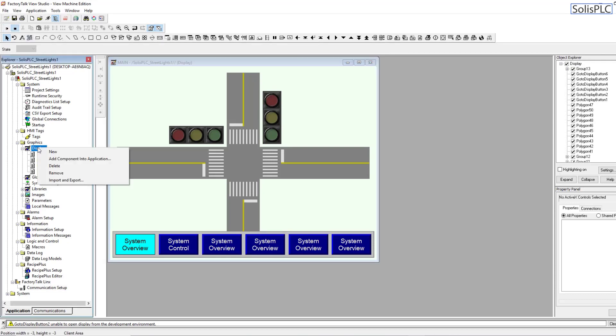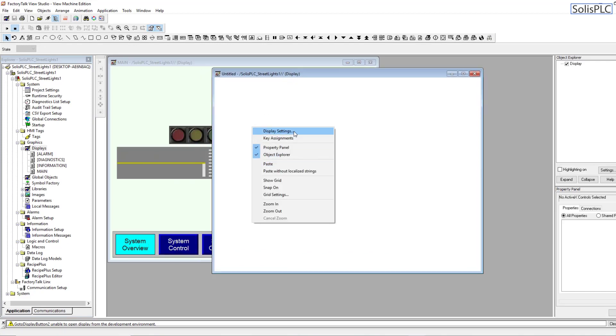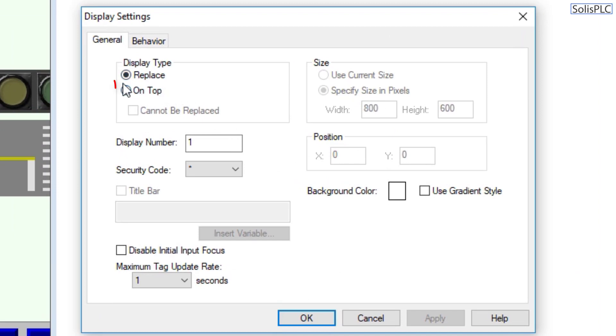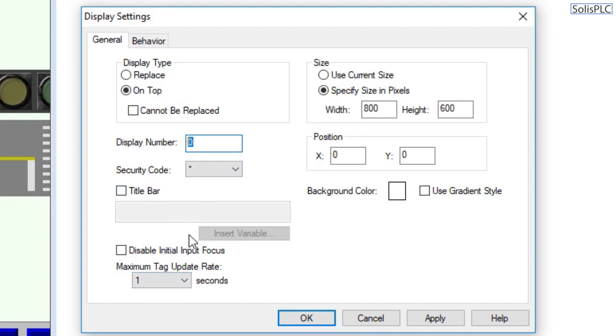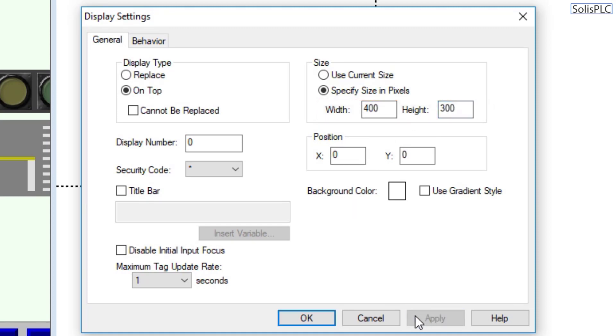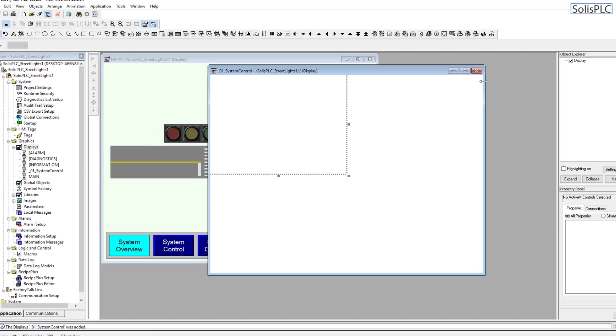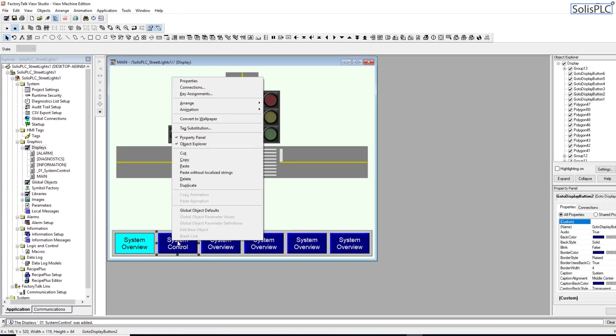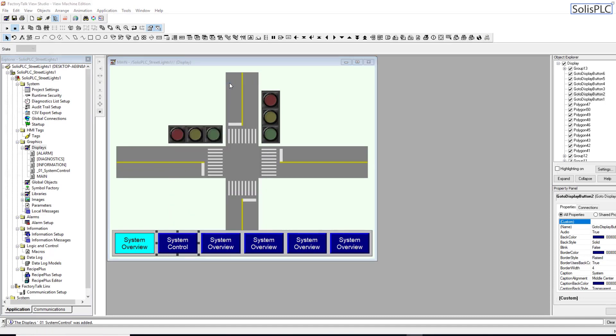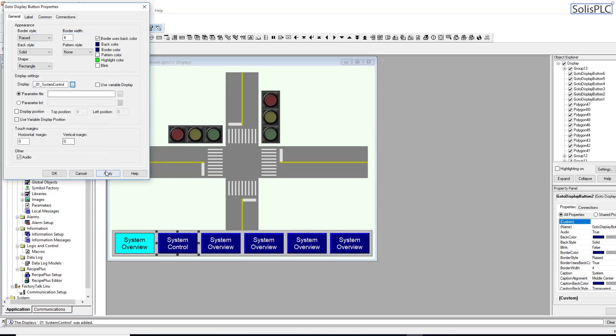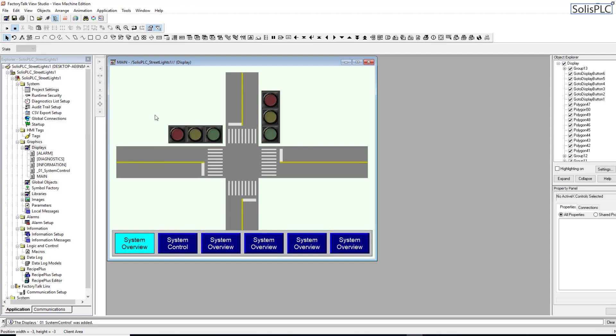Now I create a new display for the system control pop-up. In display settings, I enable the 'on top' feature to make it a pop-up, set the dimensions to roughly half the main display width and height, and hit apply. I save this display as 'underscore 01 underscore system control'. Then I go back to the System Control button, open its properties, set the target display to 'system control', and apply. The pop-up is now linked and will open when that button is pressed.